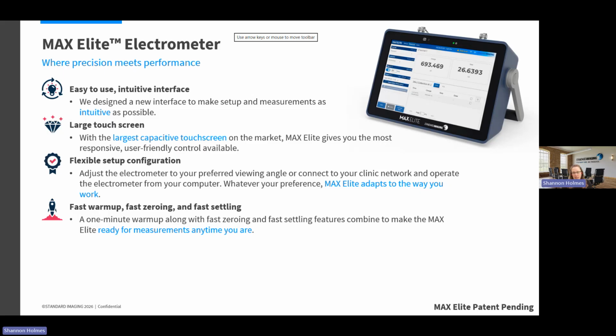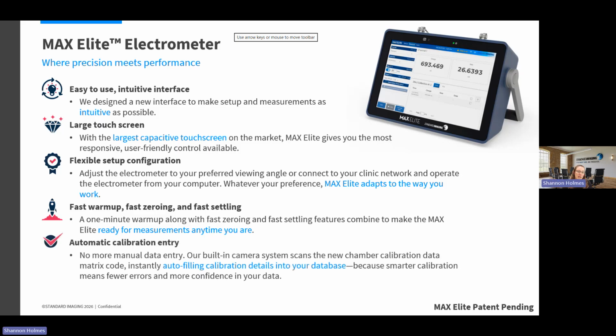It's got a fast warm up. It's ready very quickly to make measurements. We've also added fast zeroing and fast settling features to this electrometer, again so that it's very responsive and allows you to get straight to measurements as quickly as you can. There's a little camera at the top of the screen that will read data matrix codes that can now be requested as part of your chamber calibrations within the US at least. The ADCLs are providing that as a service, although usually you have to request it still. If you have a chamber calibration with a data matrix code, you can scan it and it'll automatically populate the chamber library within the MAX Elite, just again to make things a little bit smoother and easier for you.